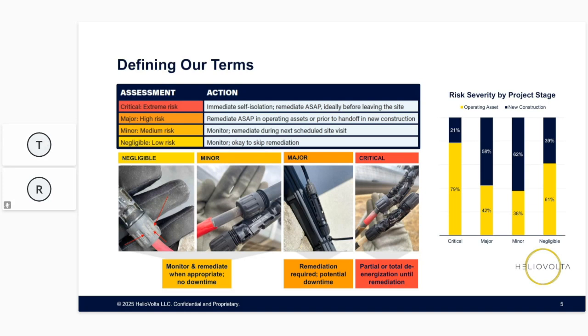But things start to change as we move to the right. In that major example, there's a field-made home run where the connector is cross-mated and under-torqued, and this is a systemic issue on site. This means there's a lot more opportunities for failure and a much higher risk of thermal anomalies as these connectors operate over time. This is a problem that should be addressed ASAP because there's just too many potential failure points to simply monitor.